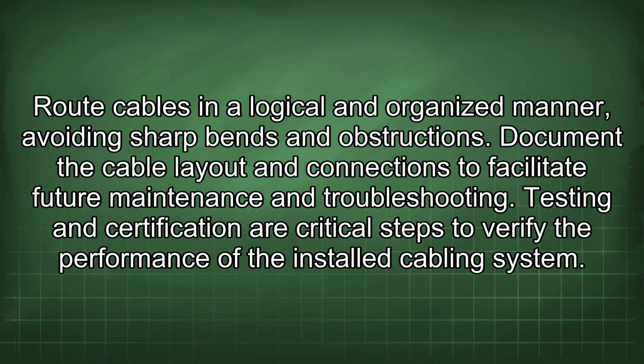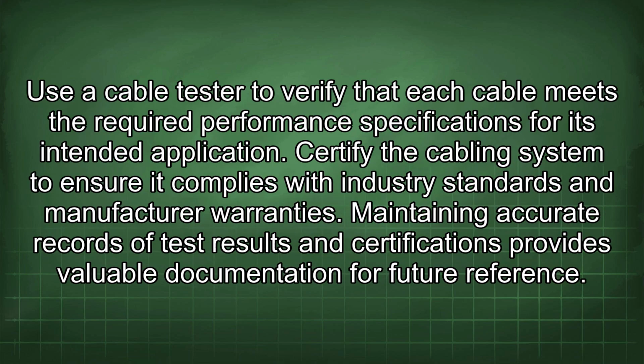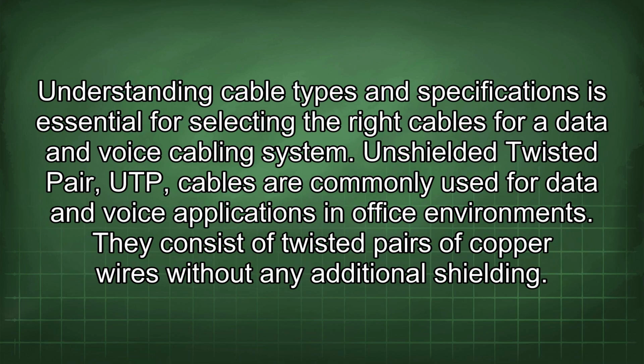Testing and certification are critical steps to verify the performance of the installed cabling system. Use a cable tester to verify that each cable meets the required performance specifications for its intended application. Certify the cabling system to ensure it complies with industry standards and manufacturer warranties. Maintaining accurate records of test results and certifications provides valuable documentation for future reference. Understanding cable types and specifications is essential for selecting the right cables for a data and voice cabling system.